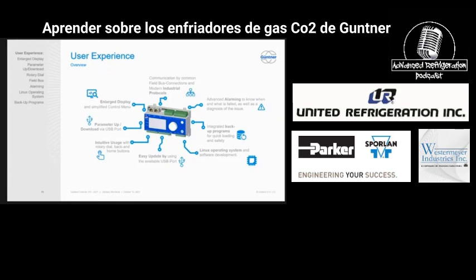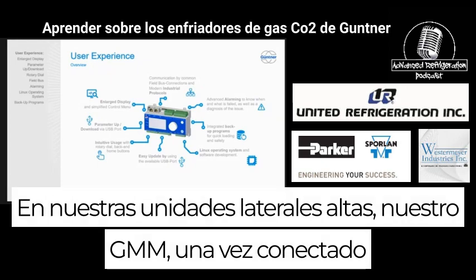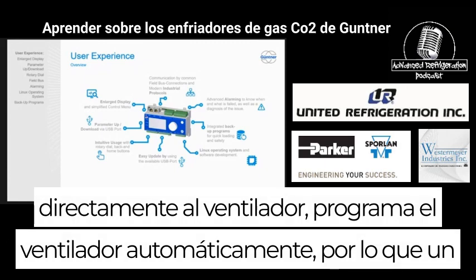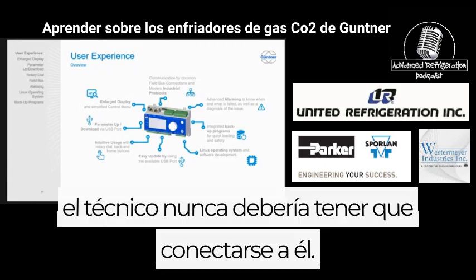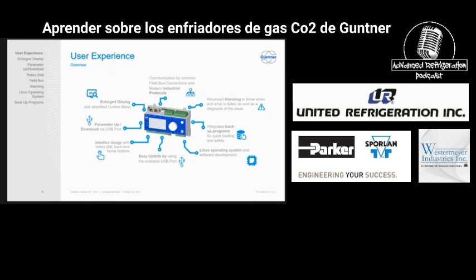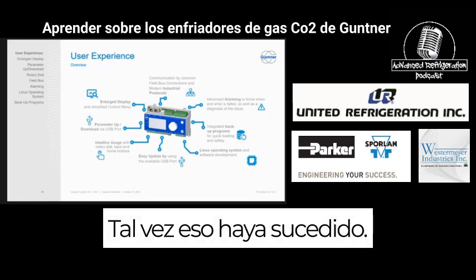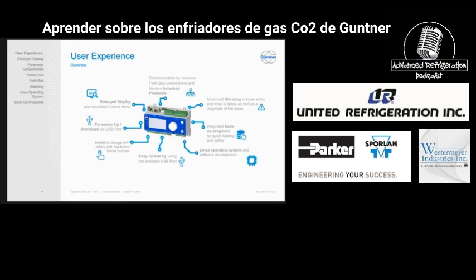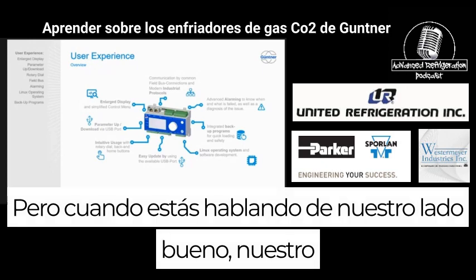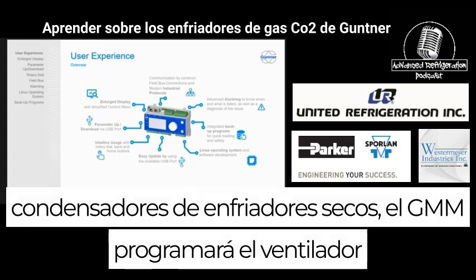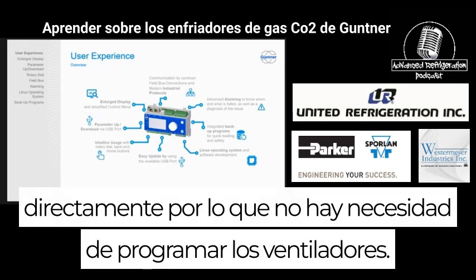So on our high side units, our GMM, once it's connected directly to the fan, programs the fan automatically. So a technician should never have to connect to it. On the low side, on the evaporators and stuff, that's a different story. That has happened. It's rare, but it has happened. But when you're talking about our high side, our dry coolers, condensers, the GMM will program the fan directly. So there's no need for programming the fans.